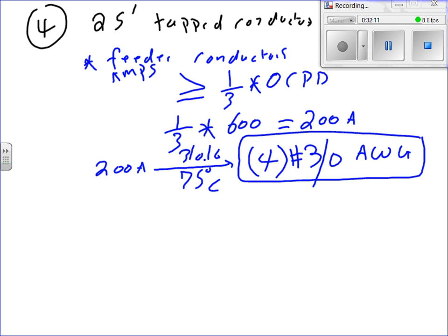Okay. I want to size the equipment grounding conductor, but I need to wait, guys, until I size the overcurrent protection device. So I'm going to go 5. Overcurrent protection device. This overcurrent protection device, everybody knows it's not at the source of the power, it's at the sink. This is at the end, not at the point where the conductor gets the power. At the end of the conductor, that one that we're sizing, all of them at the end. That's why we have tap conductors.